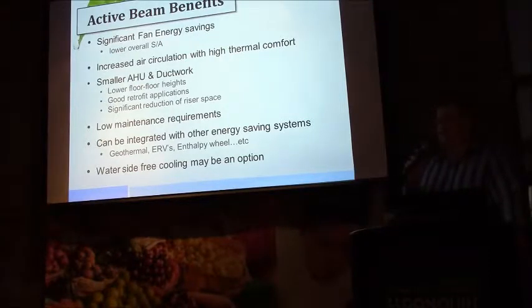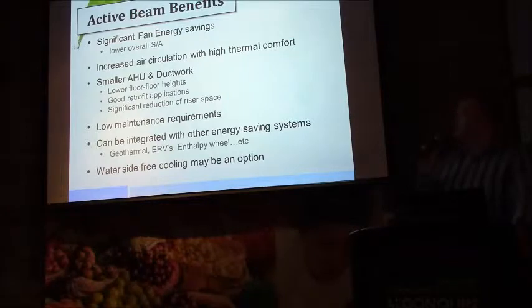Also, large district campus cooling applications also struggle with low delta T syndrome and low quality chilled water supply, where the beams are taking much warmer chilled water to them. And frankly, they can't use the colder water because it will condense. Also helps to improve the delta T across the chiller plant and improve the operating performance of that district cooling application. And so really for post-secondary education and the larger the system, obviously, as an applied system, the greater the benefit, frankly.